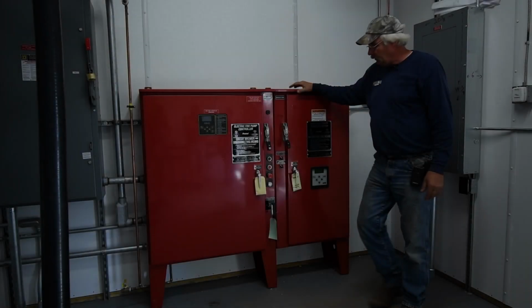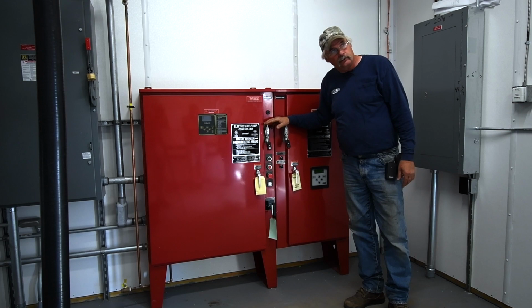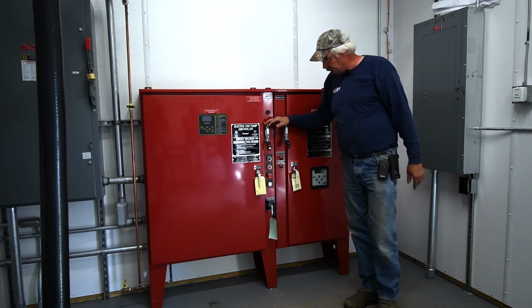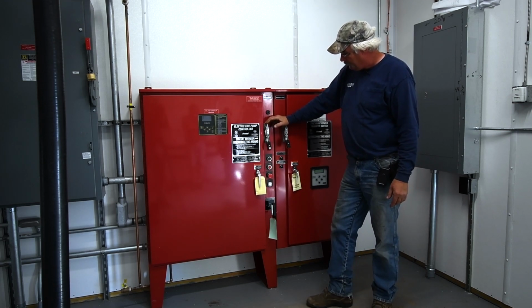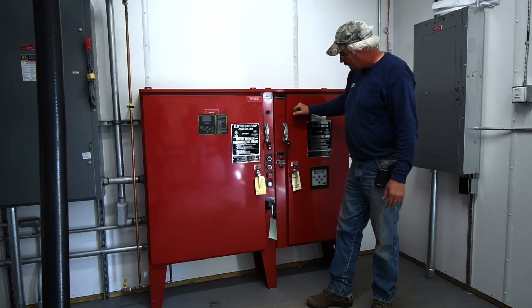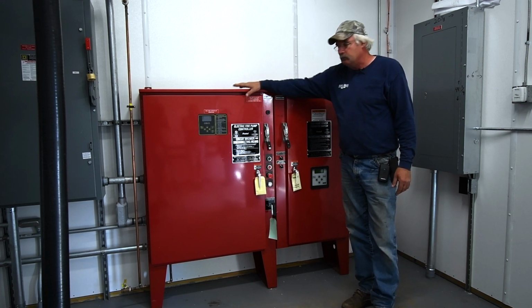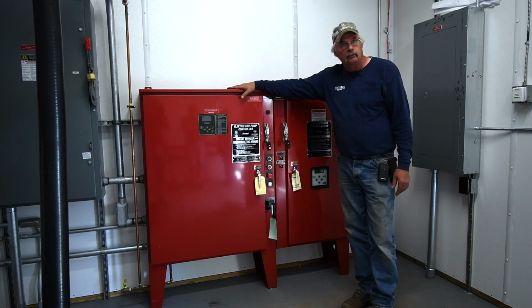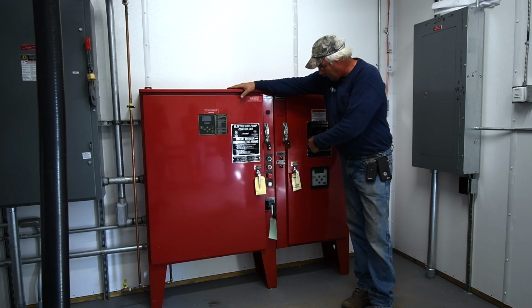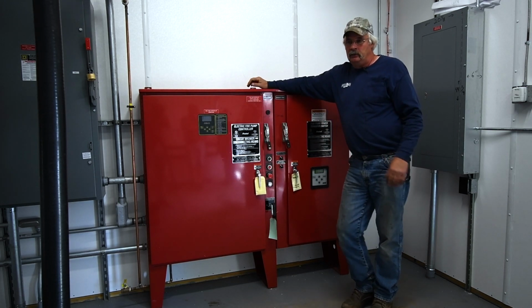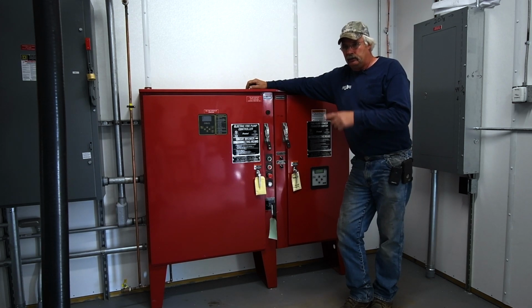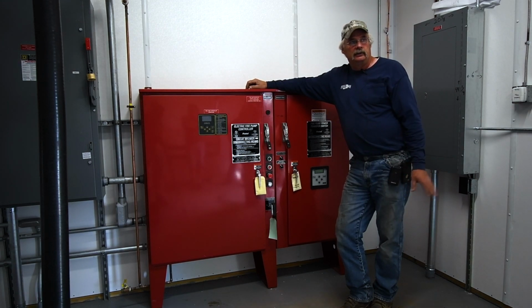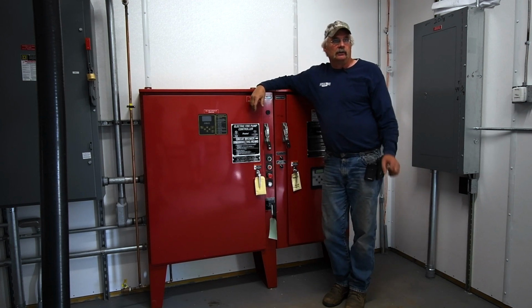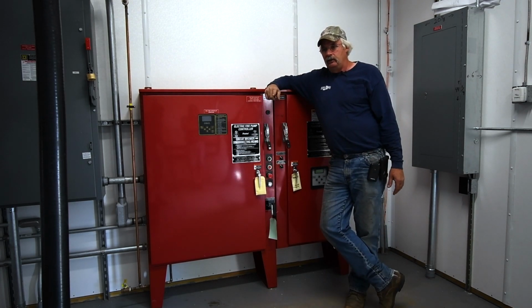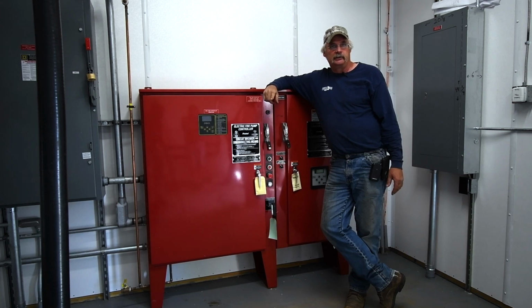Right now, this is a dual disconnect controller that feeds the fire pump. And what we have here is you have an AC power side and you have a DC power side. The DC side is if you lose your main power coming into your facility, it's got an emergency backup diesel generator. It doesn't mean that when you lose power that the fire pump's going to run. The diesel generator will kick on during a power outage. The only time that it'll actually start the fire pump is a loss of pressure.